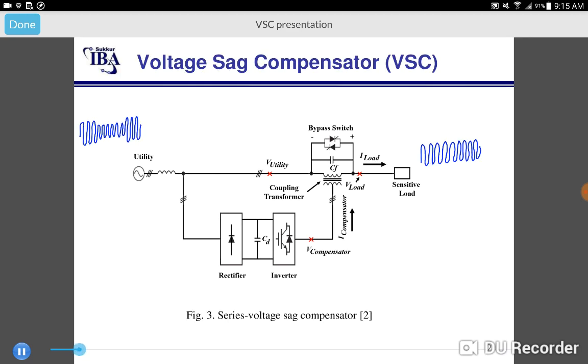A voltage sag compensator is basically a device that is used to compensate the voltage sags that are produced at the generation side due to any malfunction in the system. It comprises of an inverter, rectifier, bypass switches, and a series transformer. The bypass switches are used to bypass the series transformer during normal operating conditions. But as soon as sag occurs, the inverter is used to generate the compensated amount of voltage. The series transformer is here to add up this compensated amount of voltage with the utility line. In this way, a smooth voltage is being received at the load side.